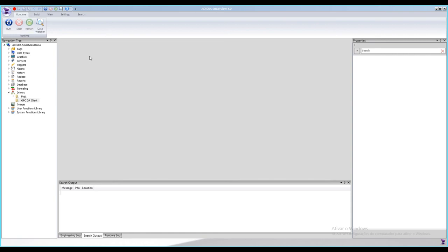SmartView is also an OPC server, so if you want to do the opposite, you have an OPC client in some other application, maybe external software, and you want to access all the information that's being held in your application, you can simply connect to the OPC server of SmartView and browse through all the tags that are here. And if the tags are enabled, you're going to be able to connect and maybe change values. You can exchange information from SmartView to different devices.